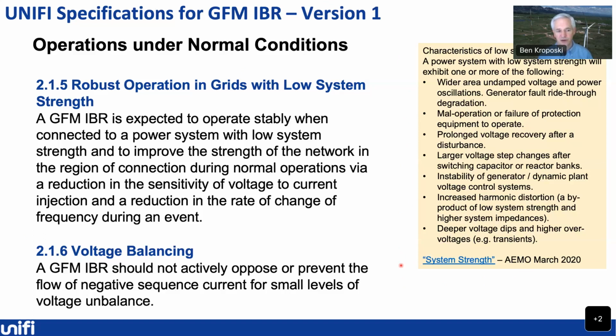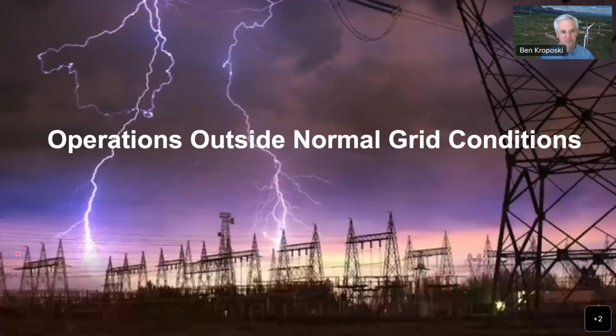Usually on a strong system, you don't have very big reactions to disturbances. And on a weak grid, you can potentially have very large reactions in voltage and frequency. And so you need to make sure that your systems are able to take that into account. And then, for example, we also want to make sure, at least on three-phase systems, that there's an ability to do voltage balancing on those systems.